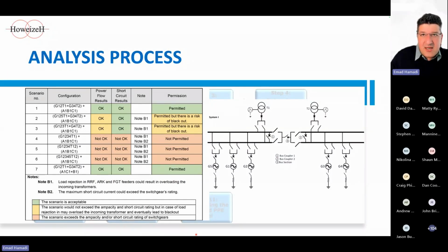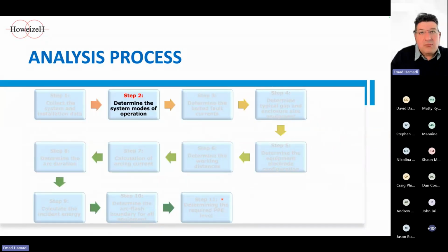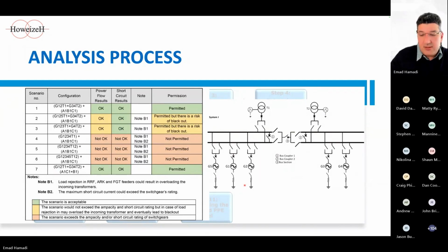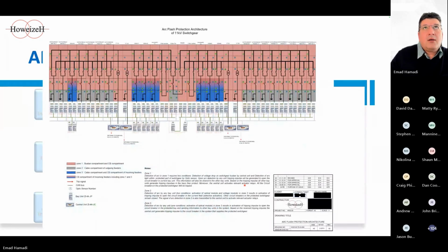I've seen on sites that designers normally put some time delay in the instantaneous overcurrent relay to allow the DC component to decay, so that the current can pass through its first zero crossing. This delay, although it's just a few cycles, could considerably increase the incident energy. For example, in this project we had this issue and we had to install excessive arc flash relays on the main bus bar to mitigate it. This is the main bus bar that we have, and you can see so many relays over there just because of that issue.